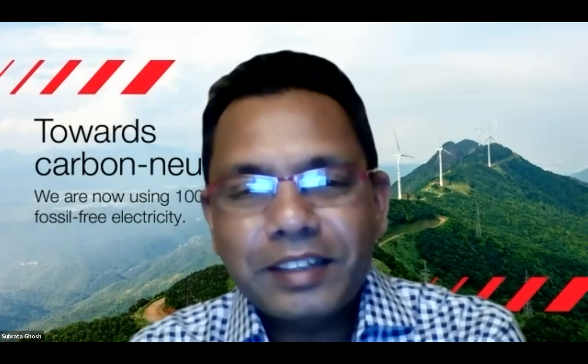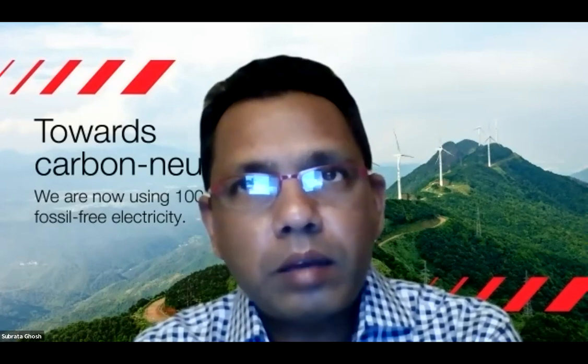Okay. Yes. Omar, how does the FFC behave against high inrush? And if two FFCs are operating in parallel mode with one FFC losing its 33 kV supply, would the second FFC start feeding the 33 kV dead network? I think that's probably a question that can be answered by the next project, because we're only working with an SFC at the moment. But I'll give you an example. There was a voltage fluctuation on the 33 kV side, high voltage from Northern Power Grid. The SFC works to a certain limit anyway. If it goes beyond that limit, the SFC just takes care of itself and shuts itself down. Going back to your question on the dual SFC, the Potteric Carr SFC is a single one. But ideally, if we had two SFCs operating in parallel, if one shuts down, the other will look after itself.